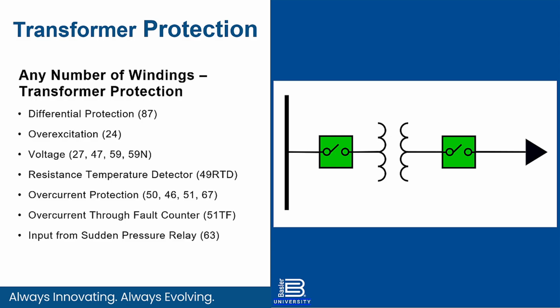Another common application is a transformer protection. So very similar to a feeder protection, has a lot of the same functions, but one of the cores to most and many transformer applications is a differential function. The differential function is looking at current in and current out and making sure they balance. With transformers, you need to make sure that you can measure all of the currents that do go in and out of that transformer. So for a two-winding transformer, that would generically be phase A, B, and C on both sides of the transformer, so 6 current inputs, but there might be 2, 3, or 4 winding transformers, even tertiary connections that might result in 12 or more current inputs needing to go into the protective relay.